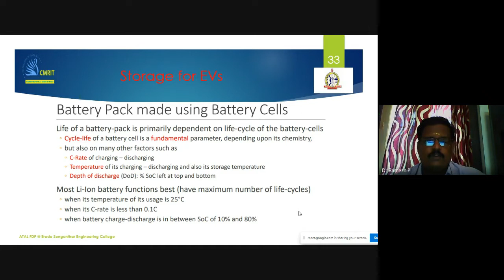Then the factors affecting battery life cycles: the rate of charging and discharging. A lithium-ion cell manufacturer guarantees a thousand cycles under conditions such as charging at a C/2 rating, discharging at C rate, at 25 degrees C with 85% DOD. The manufacturer gives the specifications, with care to be taken in charging and discharging. If you follow them, only then will you get the manufacturer's stated life cycles. If they give 1000 life cycles, you get them only if you follow the guidelines of charging and discharging rating. Suppose you do not follow them, the life cycle will decrease.